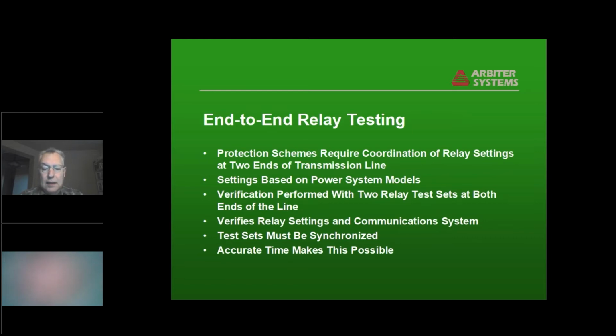In the event of many transmission line protection schemes, the protection is coordinated between the two ends of the line. They usually have data communications between them. And if you want to validate that with relay test sets, you need 2 relay test sets to generate the appropriate signals at the ends of the line. But the test sets have to be synchronized. So when you generate a simulated event to verify the relay, they both have to do the same thing at the same time. So it's another application that accurate time makes possible.